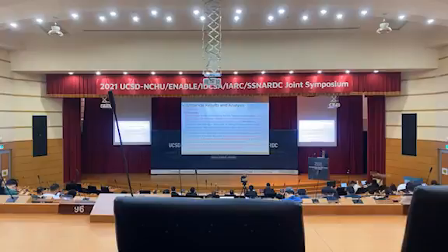Currently, the university farm has contracted with Taipower, and the model covered 77, 78, up to 150 kilowatt. And it came out that the optimal strategy for the farm is to adjust the regular contracted capacity from 76 kilowatt to 119 kilowatt, without doing anything, just changing the contract capacity. Then the electricity bill could be reduced, if the farm adopted the 3-block time of use rate instead of the currently original 2-block time of use rate.